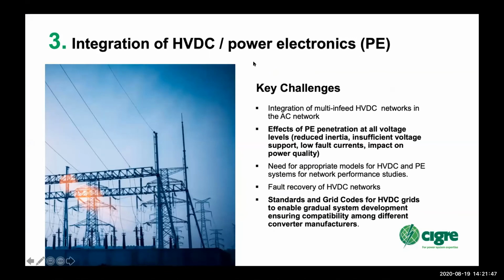It's not only HVDC, it's also MVDC and LVDC. It's really the integration of multi-infeed networks into the AC networks at the HV level. Then there are the effects of power electronic penetration at all voltage levels, including reduced inertia, insufficient voltage support, low fault currents, and impact on power quality, especially with low-cost inverters that might be coming in. So we need appropriate models, fault recovery of HVDC networks, and standards and grid codes for HVDC grids.